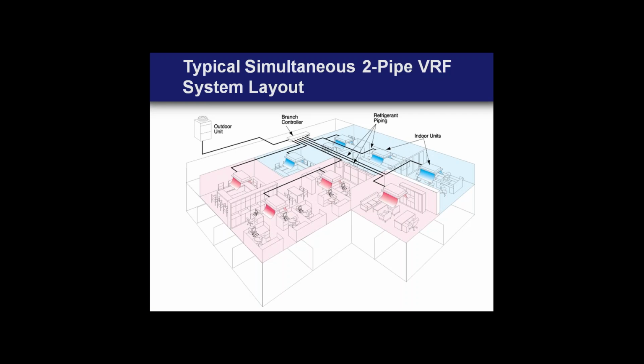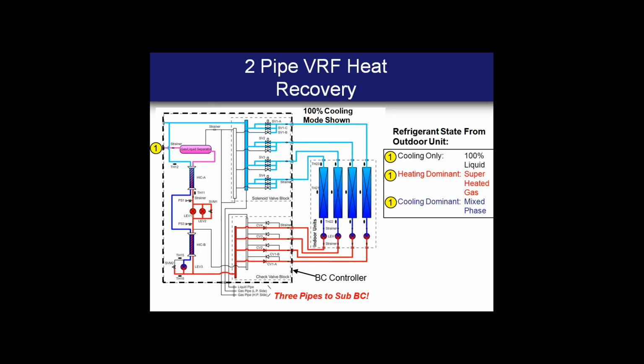And then there are some tube-in-tube heat exchangers inside of that device that actually provide what we call medium pressure liquid. And that is your cooling liquid that is being subcooled that's sent out to indoor units in cool when you're in this cooling dominant heat recovery mode. Looking at the BC controller in this dark dashed line, which is what's represented on the screen, again, you can see some of these major components: the gas liquid separator, the tube-in-tube heat exchanger.